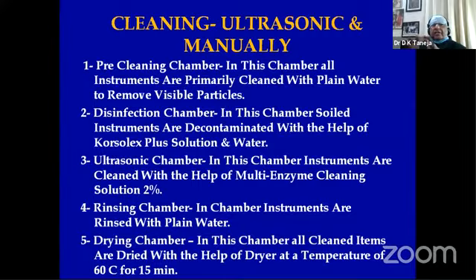So you have a pre-cleaning chamber. In this chamber, all instruments are primarily cleaned with plain water to remove any visible particles. So just put plain water, it will get clean. Then the disinfection chamber, the second chamber. In this chamber, the soiled instruments are decontaminated with the help of Korsolex Plus solution and water. Then you have an ultrasonic chamber. In this chamber, the instruments are cleaned with a multi-enzyme cleaning solution at 2% strength. Then you have a rinsing chamber, where instruments are rinsed with plain water.